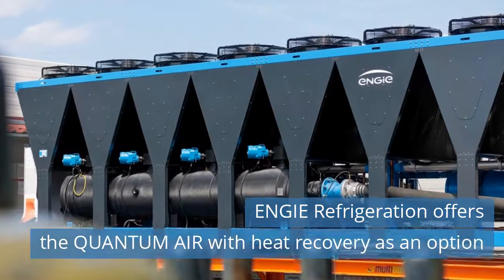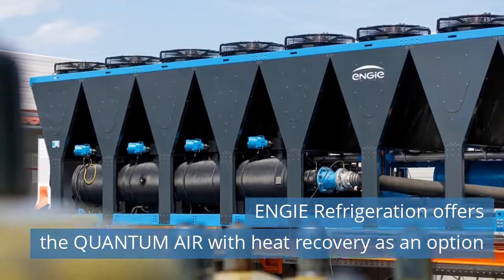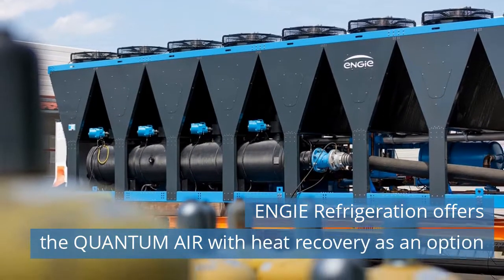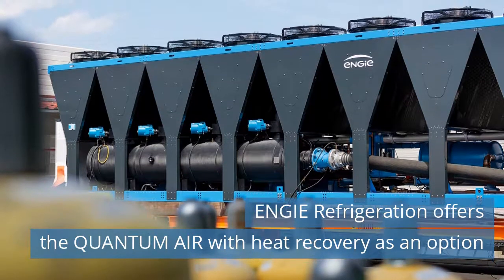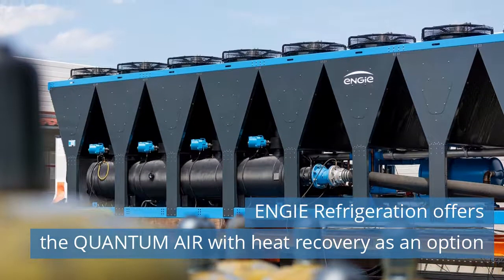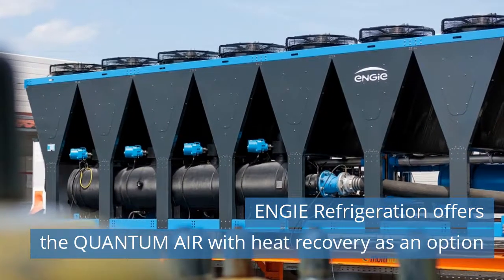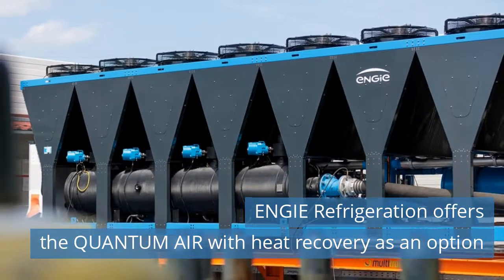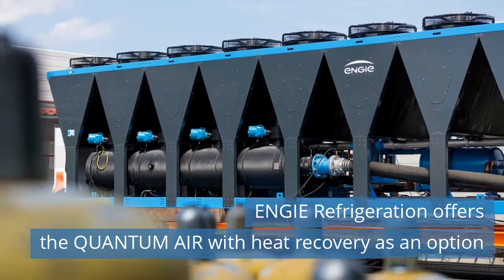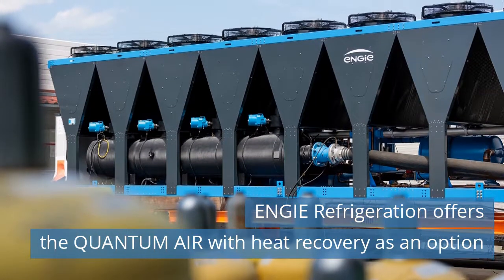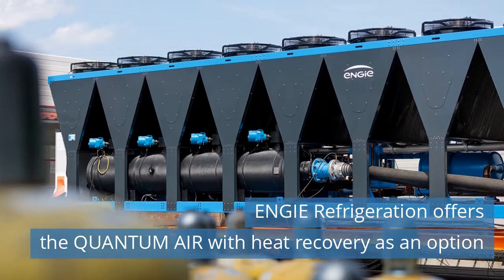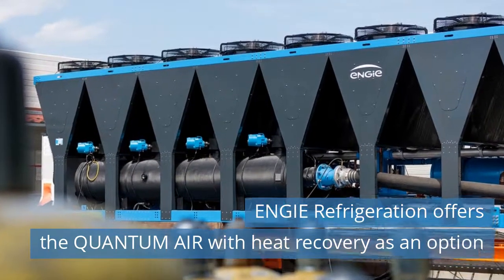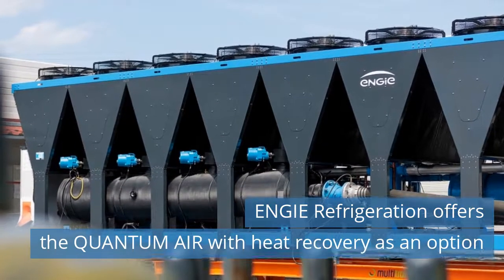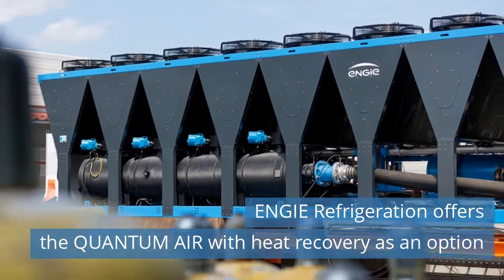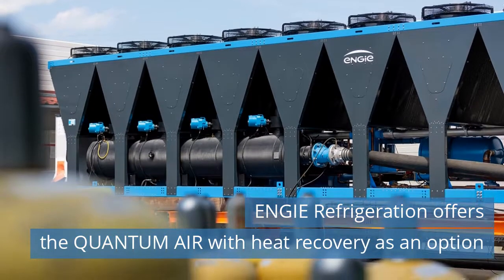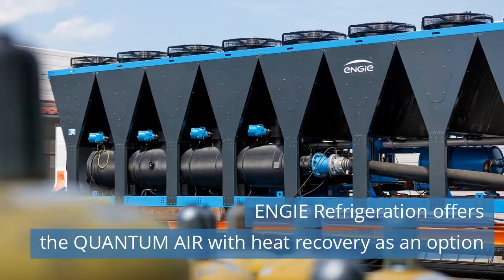ENGIE Refrigeration offers the Quantum Air with heat recovery as an option. Quantum Air chillers from ENGIE Refrigeration are now available with optional heat recovery. Customers can reuse up to 100% of the waste heat generated during the cold generation process and use it for heating purposes, for example. This reduces resource use and improves energy efficiency. The feature is especially interesting for industrial enterprises, data centers, hospitals, and hotels. ENGIE Refrigeration now offers a forward-looking solution with its Quantum Air chillers with heat recovery as an option. Water-cooled Quantum chillers have been available with optional heat recovery for many years, and customers are still running them successfully. As this feature has many advantages, ENGIE Refrigeration now offers it for the Quantum Air as well.